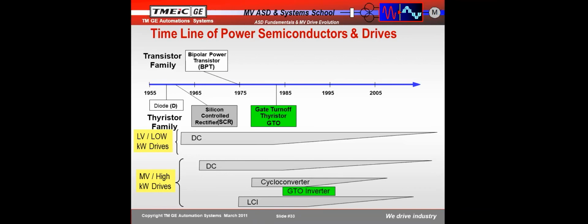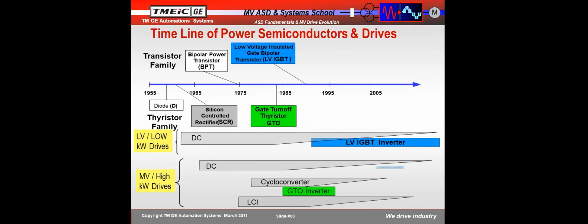Now we're back on the bottom part of the line, and frankly, we don't want to be on the bottom of that line. We want to be on the top of that line, because if you have to find ways of reversing the current or injecting huge amounts of current into the gate to turn it off, that just makes for a drive that is more complicated and less reliable. But the gate turn-off thyristor could do what we couldn't get a transistor to do. And so in the early 80s, a lot of drives, both low voltage and medium voltage drives, started to use gate turn-off thyristors. Then we came out with the IGBT.